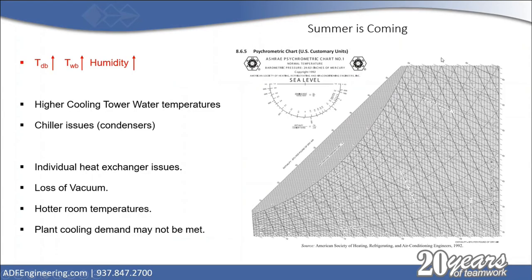Summer is coming — that's the theme of this presentation. With summer, you get higher dry bulb temperatures, higher wet bulb temperatures, and obviously higher humidity. The hotter your air gets, the more water it's able to hold. And so what you get is higher cooling tower water temperatures, as you all may have experienced. Cooling towers are a function of wet bulb temperatures, so as the wet bulb temperature goes up, your cooling tower supply water temperature goes up, and you might experience chiller issues.